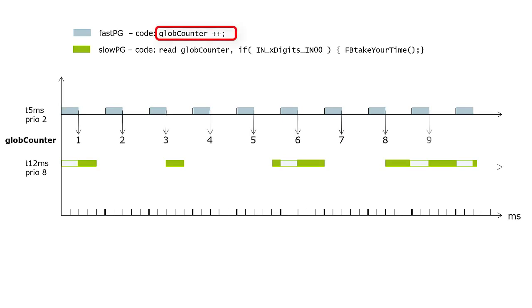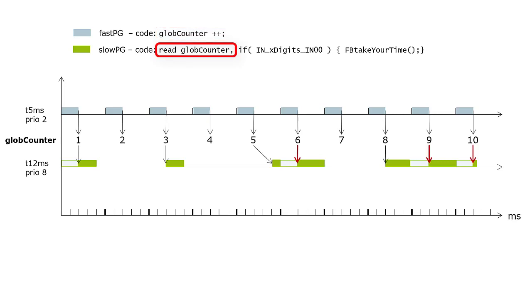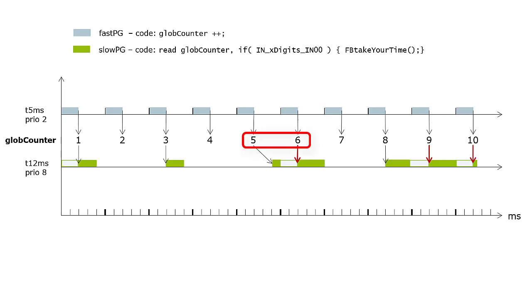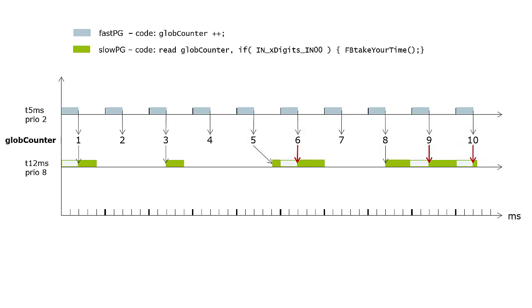The FAST-PG increments a global variable read by the SLOW-PG. You see that there could be data inconsistency if the SLOW-PG on a lower priority task is interrupted by FAST-PG on a higher priority task. This will happen if the function block utilizes too much computation time. Then SLOW-PG will get different values of the global variable in the same cycle. With data interchange via the global data space, the GDS, this can't happen.